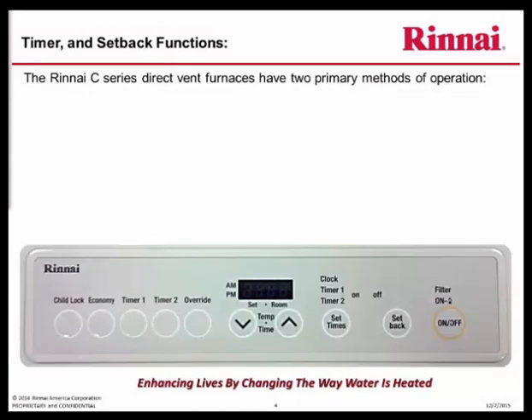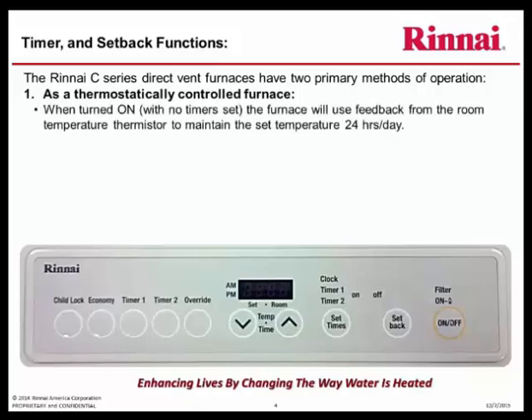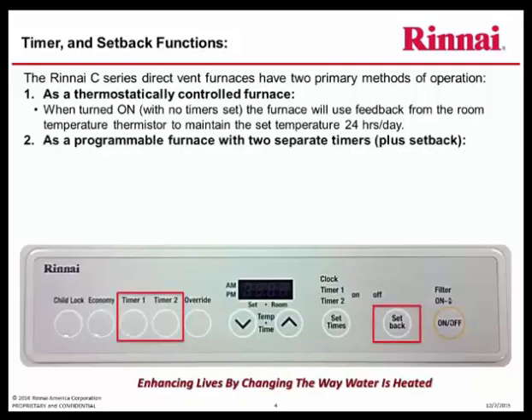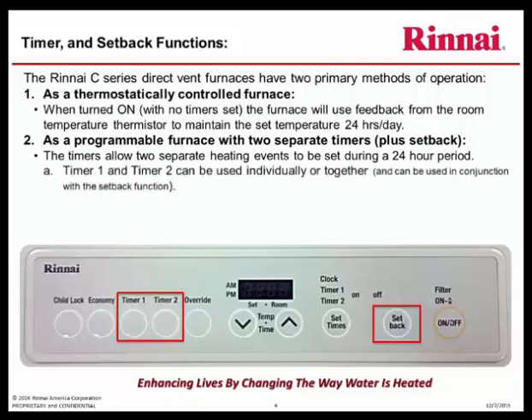The Rinnai C-Series direct vent furnaces have two primary methods of operation. One, as a thermostatically controlled furnace — when turned on with no timers set, the furnace will use feedback from the room temperature thermistor to maintain the set temperature 24 hours a day. And two, as a programmable furnace with two separate timers plus the setback. The timers allow for two separate heating events to be set during a 24 hour period. Timer 1 and timer 2 can be used independently or together, and can be used in conjunction with the setback function.